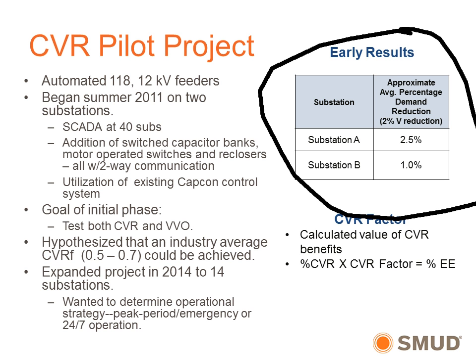Based on the results of this project, we went ahead and did CVR on 14 substations. From that we calculated what's known as a CVR factor, a conservation voltage reduction factor. See right here, the CVR-F. We theorized we could get between a 0.5 and 0.7 CVR factor.